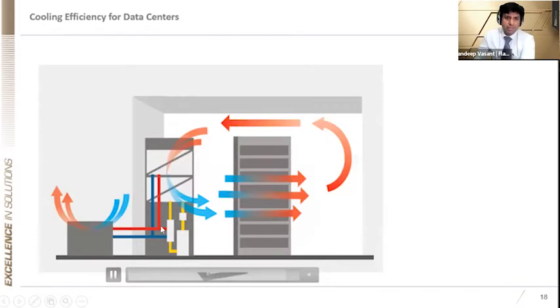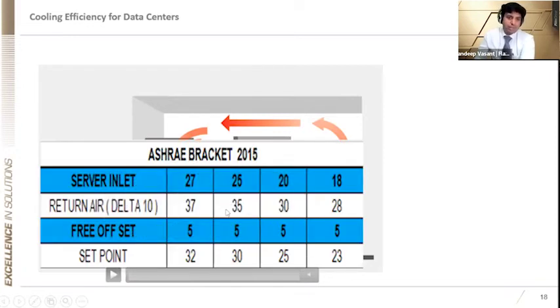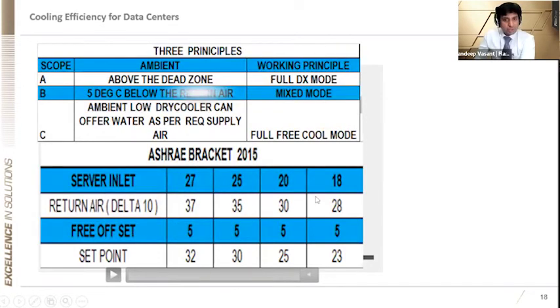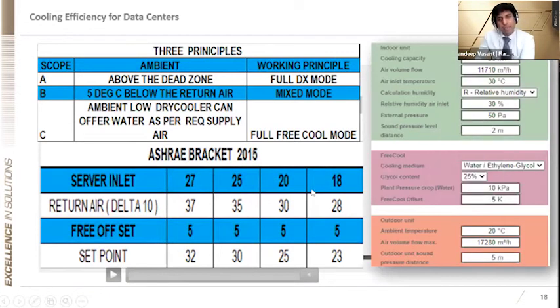As I said, there is a PAC unit, rack, a condenser, and a water circuit, and then there is a copper pipe which circulates the gas, or it can be chilled water. The outside air is not taken inside the data center. So to pull back that ASHRAE document, 18 to 27, the principle of working of the indirect free cooling unit is simple. I've taken a case study of the supply air temperature, return air temperature of 30, and RH, external ESP. This is just for our discussion purposes.